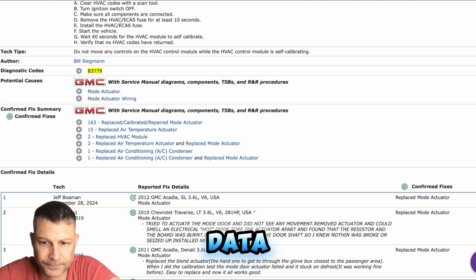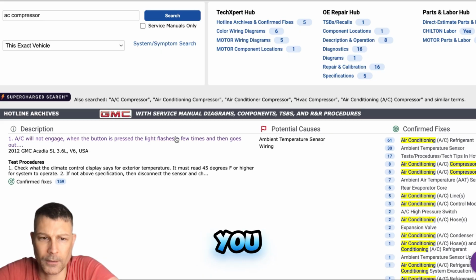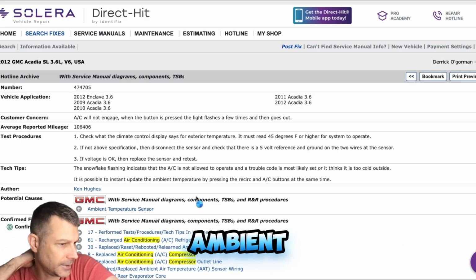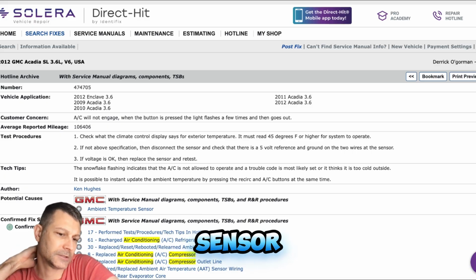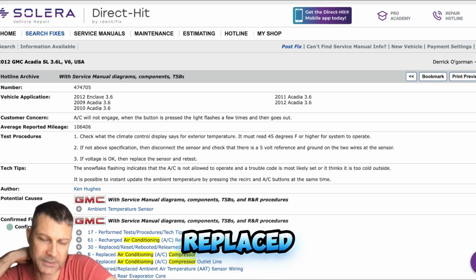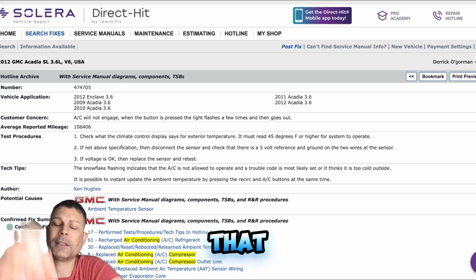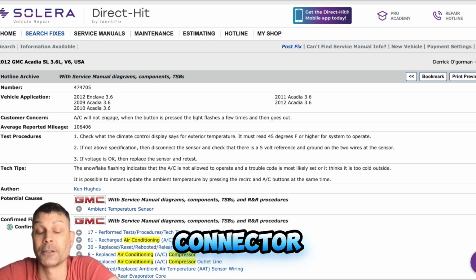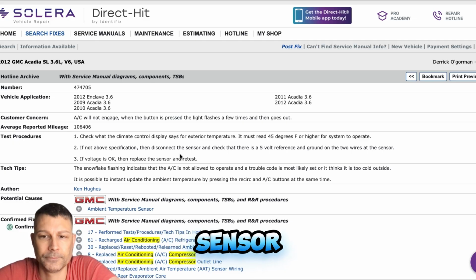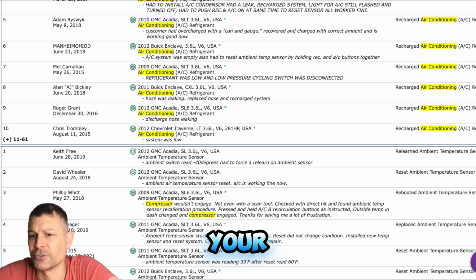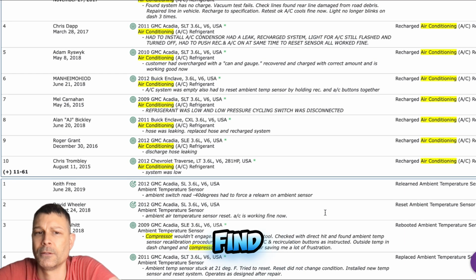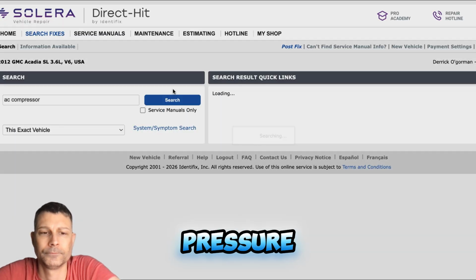All right, let me get data display. Now, which sensors were you saying I need to look at? There were 3 of them. It was the ambient air temperature sensor, the evap temp sensor, and the pressure sensor. I think you replaced the pressure sensor, but I had indicated that we got to check the circuit and the connector. The evap temp sensor is reading about 93. And what does your pressure sensor read? I've got to find it. It just shows low pressure switch open.